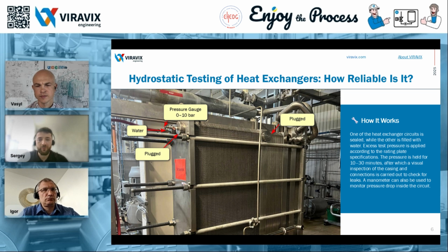Another drawback is the labor-intensive preparation. You need to seal the circuits, fill the system with water, and remove all the air. And it's important to remember, in practice, it's nearly impossible to eliminate all the air from a heat exchanger. Since air is compressible, this can affect the accuracy of the test. This may lead to inaccurate or misleading test results. It also requires time to drain the water after the test. And for certain processes, the heat exchanger must be dried afterward, which can be critical for some types of production.